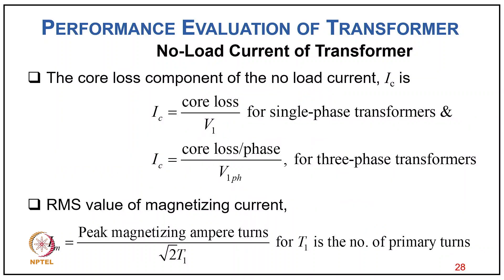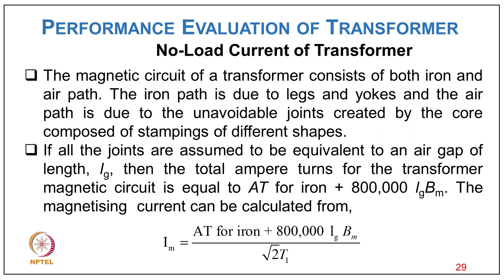The core loss component of no-load current Ic = core loss / V1 for a single-phase transformer, and Ic = core loss/phase / V1ph for a three-phase transformer. The RMS value of magnetizing current Im = peak magnetizing ampere-turns / (√2 × T1), where T1 is the number of primary turns. The magnetic circuit consists of both iron and air paths — iron from legs and yokes, and air from unavoidable joints.